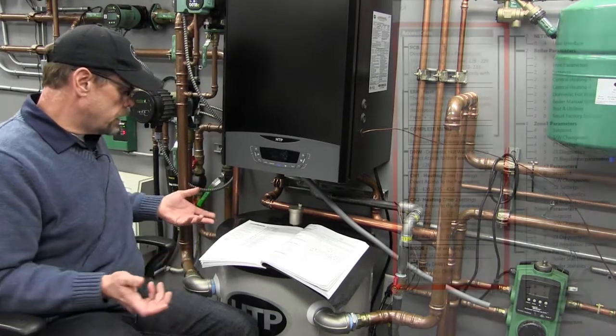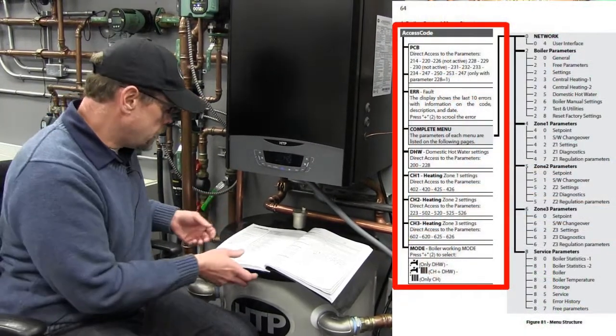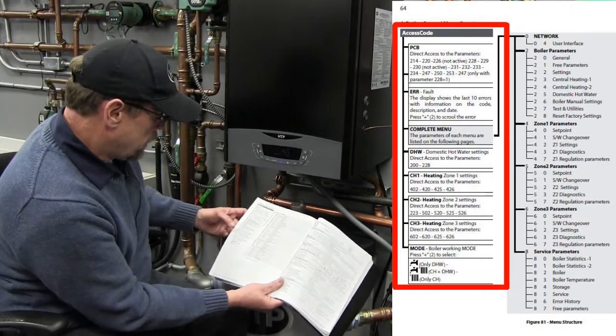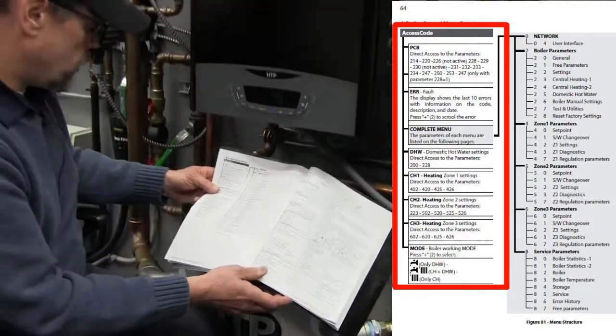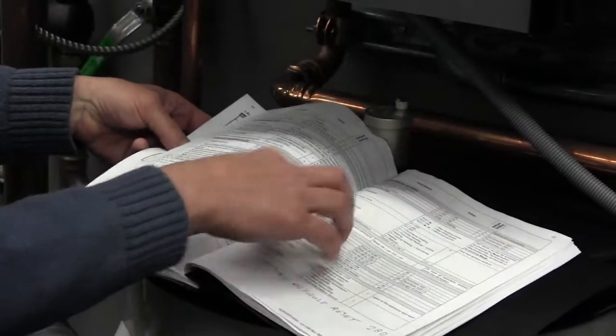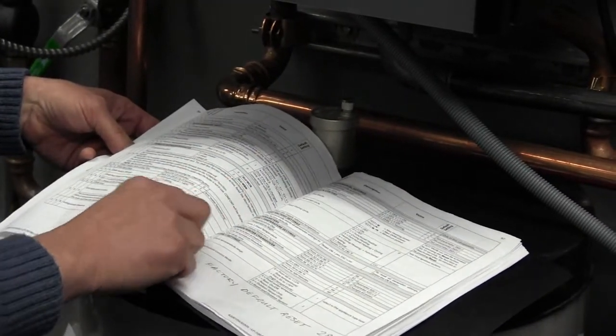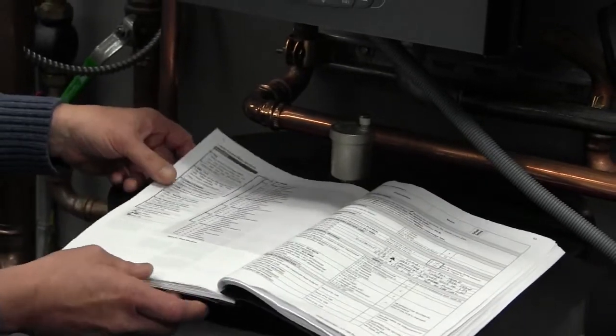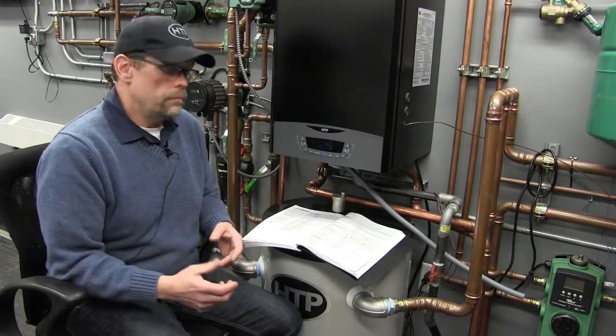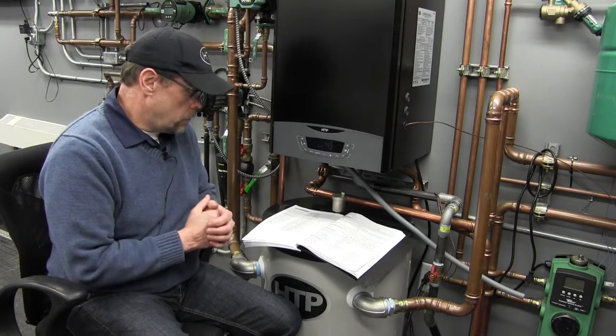In this case, let's take a look at our zone 1 or CH1 heating. In our quick access guide, it gives us these 4 parameters that we need to check: 402, 420, 425, and 426. The 400 series correlates with zone 1 temperature. They're asking whether we're operating a high temperature or low temperature system, what our set point is, and our maximum and minimum if we utilize the outdoor strategy. That's fine, and that's all we need. That will get us up and running, and we're good.